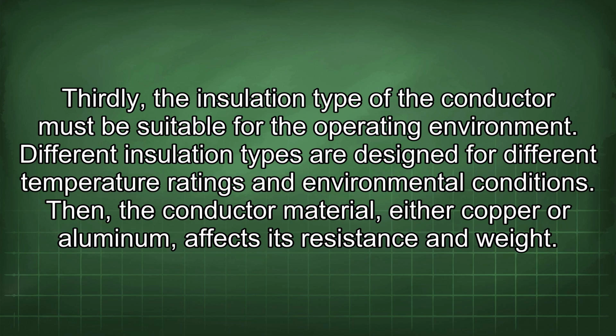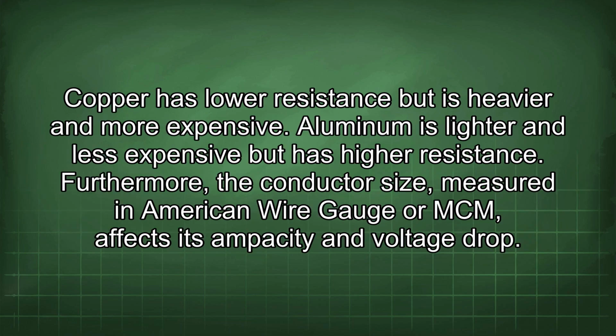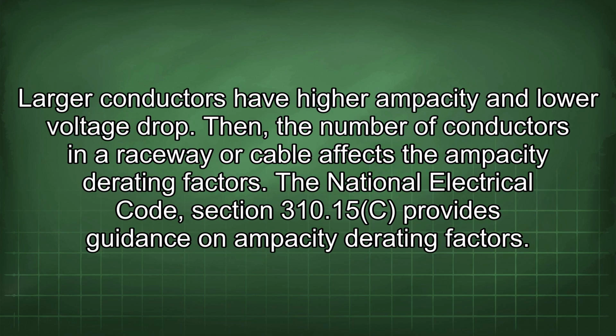Then, the conductor material, either copper or aluminum, affects its resistance and weight. Copper has lower resistance but is heavier and more expensive. Aluminum is lighter and less expensive but has higher resistance. Furthermore, the conductor size, measured in American wire gauge or MCM, affects its ampacity and voltage drop. Larger conductors have higher ampacity and lower voltage drop. Then, the number of conductors in a raceway or cable affects the ampacity derating factors. The National Electrical Code, Section 310.15(C) provides guidance on ampacity derating factors.